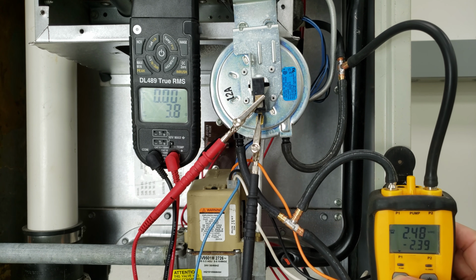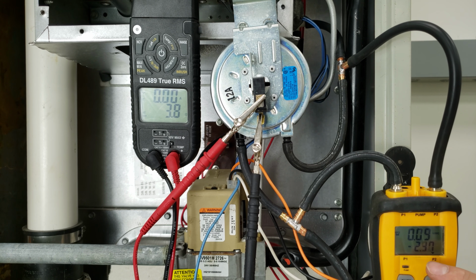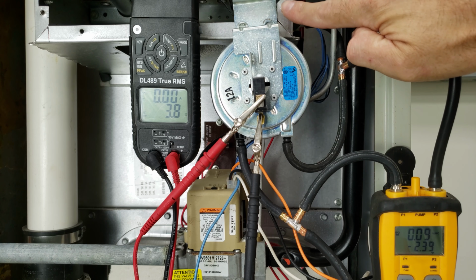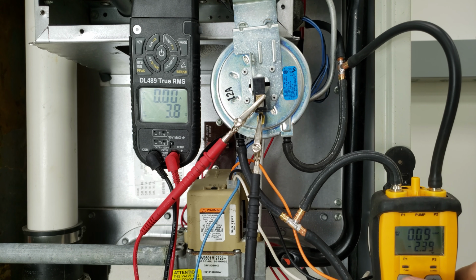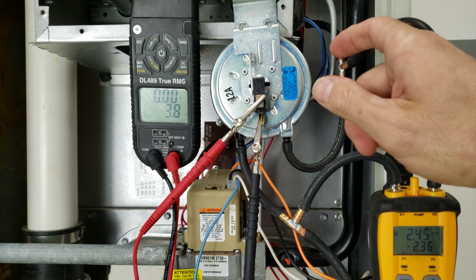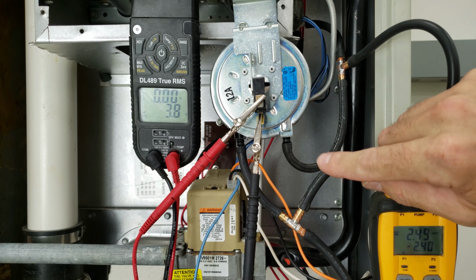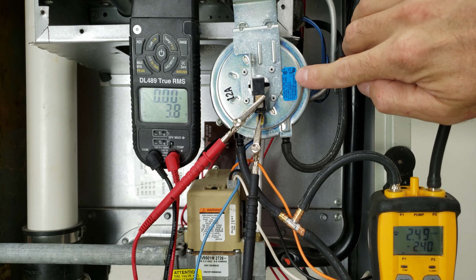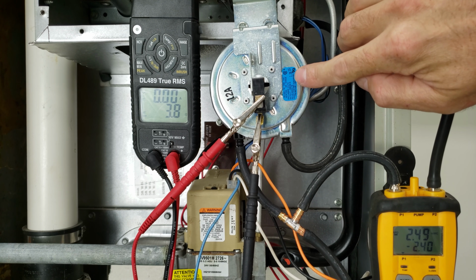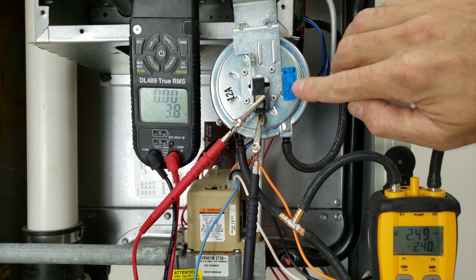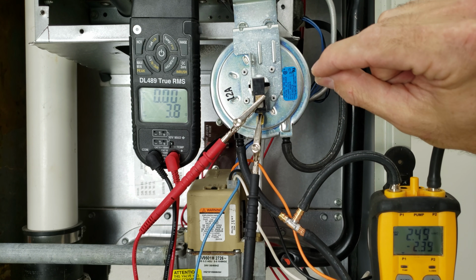And then if we were to switch to P2, we're measuring 0.09 inches of water column, and that's because this combustion chamber door over here is open. And so if we just come right back over here, we see our differential of 2.4 inches of water column across this pressure switch. Anything greater than 1.38 inch of water column, like on the rating plate right here, is going to cause the normally open set of contacts to close.